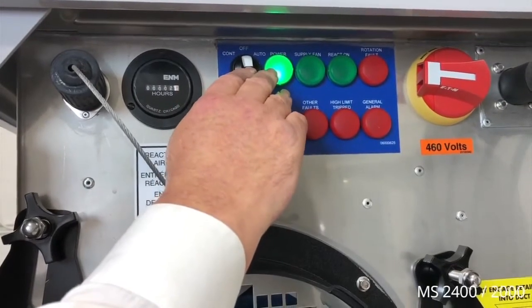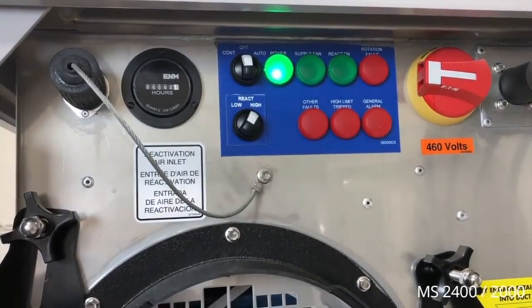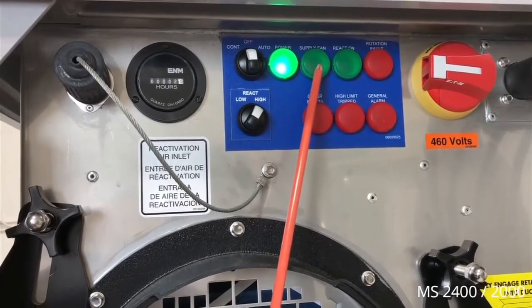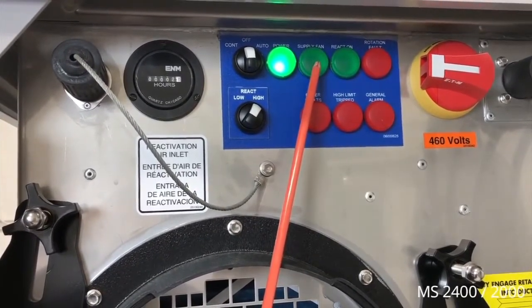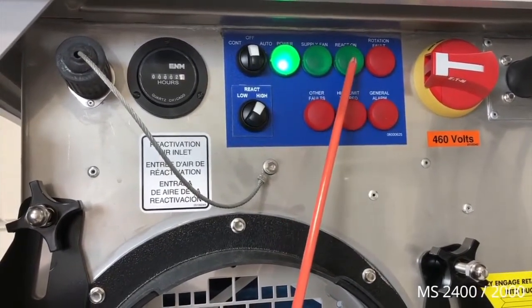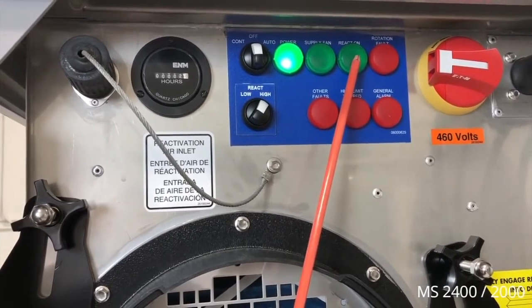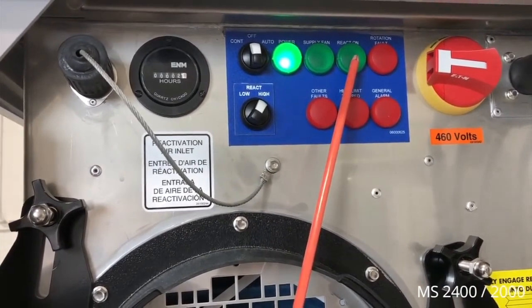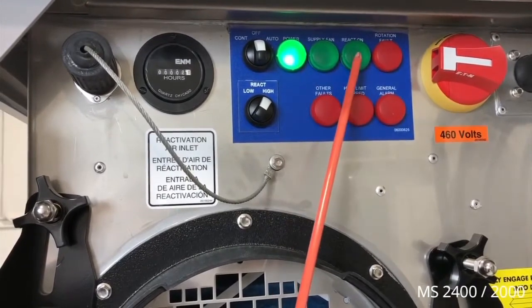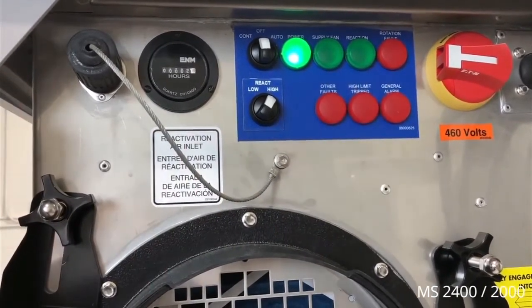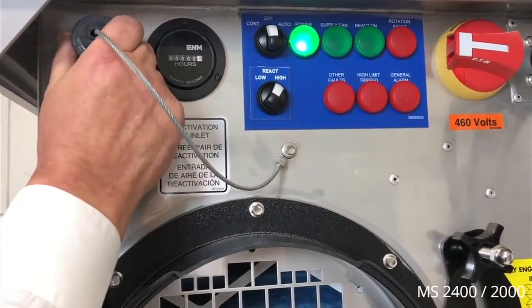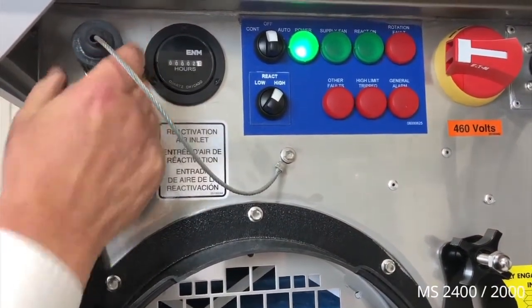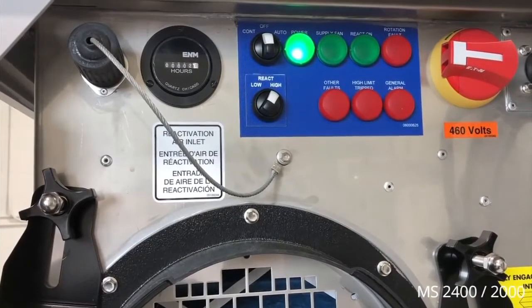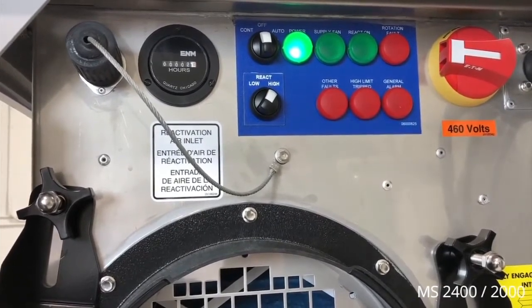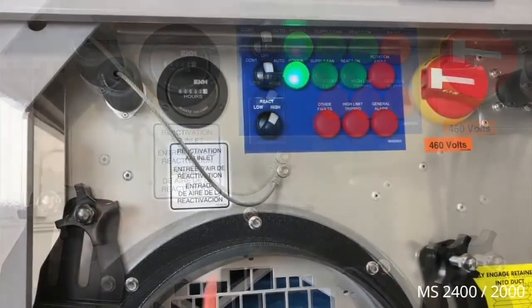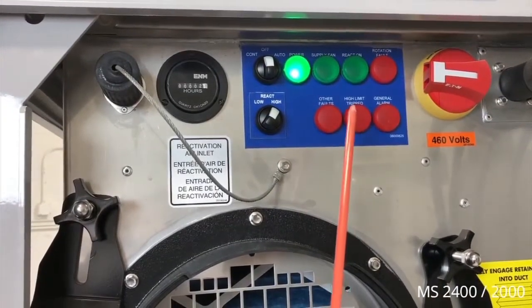When we do this, the microprocessor will first start the supply fan. The light will indicate green after it hits RPM. Then we'll start the reactivation fan, and the light will indicate green when we reach RPM. If the supply fan or the reactivation do not light, it could be possible that the humidistat plug is loose or disconnected, or the unit is connected to a remote humidistat, which would cause the unit to cycle on or off. There are 4 fault lights that indicate a problem with the unit.